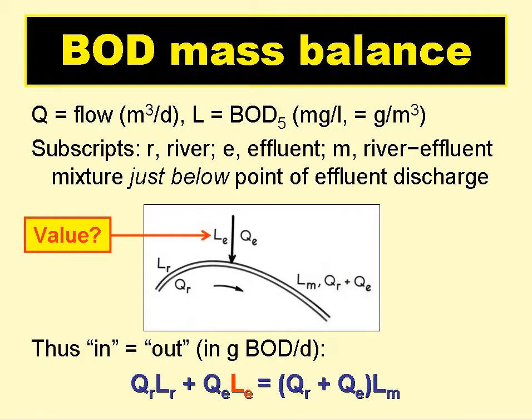The commissioners then set about determining the maximum permissible BOD of a treated wastewater to be discharged into a river. To do this, they considered a mass balance of BOD. Basically, this says that just downstream of the point of discharge, what goes in must come out. What goes in is the BOD in grams per day due to the river water upstream and the wastewater effluent, and this has to equal what comes out — the BOD, again in grams per day, of the downstream river water–effluent mixture.